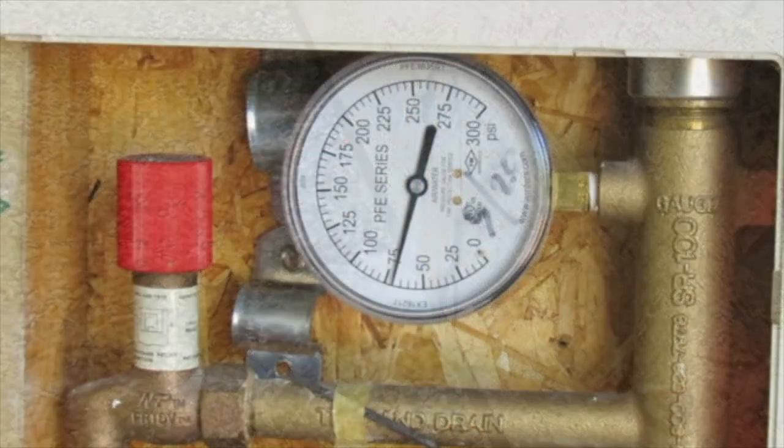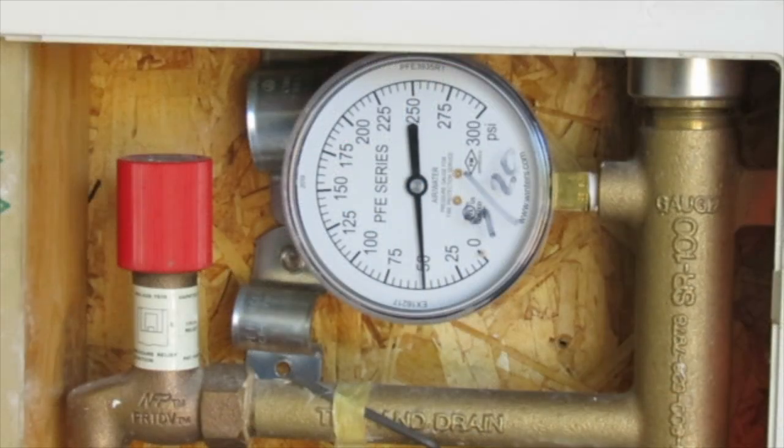At the fire riser panel, the flow switch will detect the high flow, activating the fire bell, and the fire pressure gauge will lower to about half of the initial reading while flow is in progress. If there are no obstructions in the line, the flushing water flow will continuously be under significant pressure and velocity the whole time that flushing valve is open.